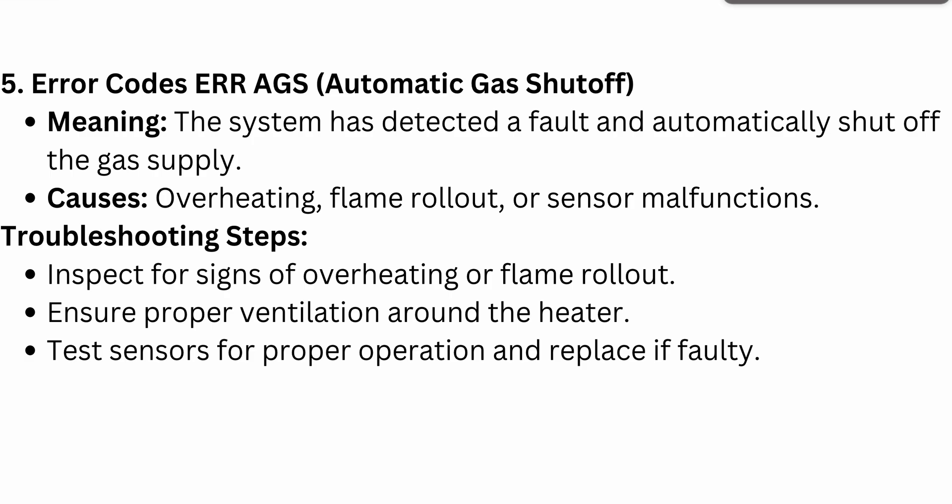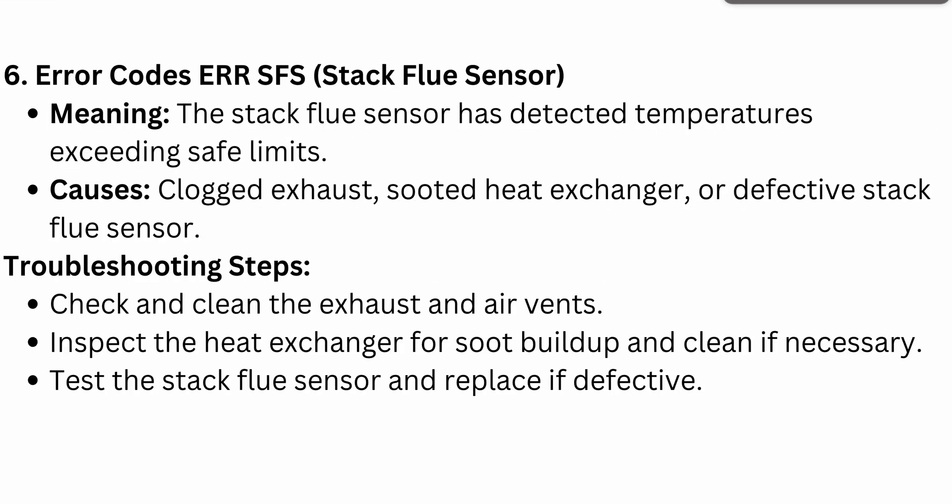The next error code is ERR SFS — stack flue sensor. It means the stack flue sensor has detected temperatures exceeding safe limits. The causes can be a clogged exhaust, soot buildup in the heat exchanger, or a defective stack flue sensor. To troubleshoot, check and clean the exhaust, inspect the heat exchanger for soot buildup and clean if necessary, then test the stack flue sensor and replace if found defective.